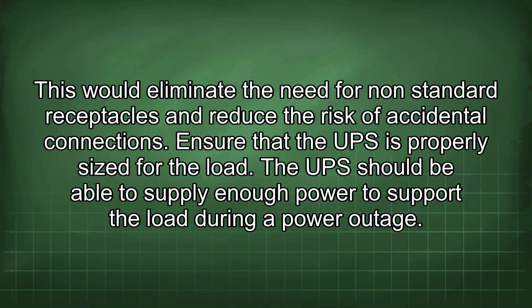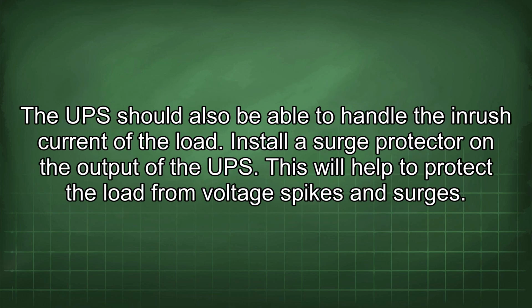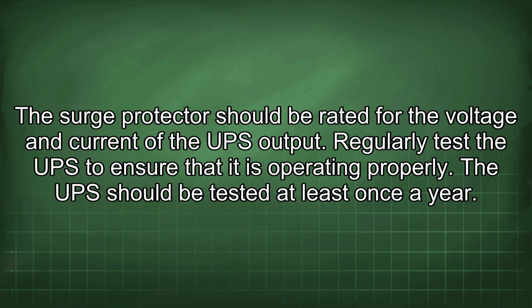Ensure that the UPS is properly sized for the load. The UPS should be able to supply enough power to support the load during a power outage. The UPS should also be able to handle the inrush current of the load. Install a surge protector in the output of the UPS. This will help to protect the load from voltage spikes and surges. The surge protector should be rated for the voltage and current of the UPS output.